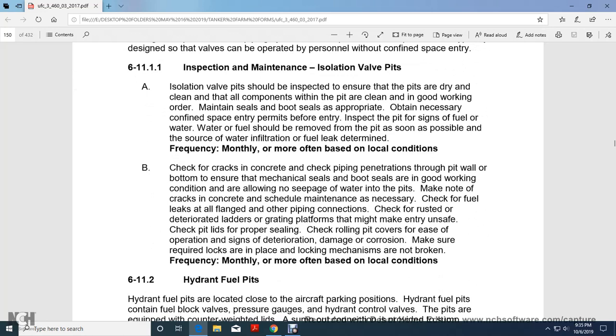Isolation valve pits should be inspected to ensure that the pits are dry and clean, with all components in the pit clean and in good working order. Maintain the seal with the boots. Obtain necessary confined space entry permits before entry. Inspect the pits for signs of fuel. Water or fuel should be removed from the pit as soon as possible. The source of the water infiltration or fuel leak should be determined. Inspect frequently, monthly or more often based on local conditions.